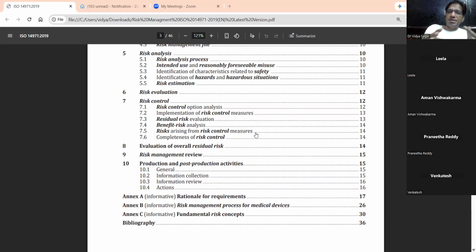Because they are sitting on the same parameter, it could be anything like the thickness of the device or longitudinal stiffness of the device or surface finish of the device. Based on the device, you can look at the recoil of the device, and I can tell you a lot of things where the performance and the risk sit on the same parameter. If you touch it, it will create havoc. During that situation, you need to find a fine balance: without decreasing the performance of the device, how can you bring down the risk? Are there any other secondary factors, or do you want to keep the risk as such? So there is a lot of thinking that goes on.